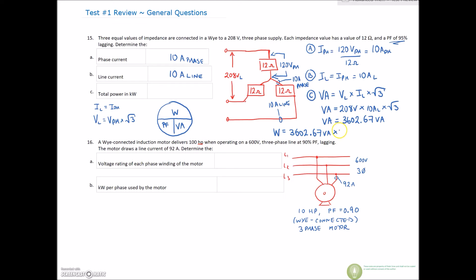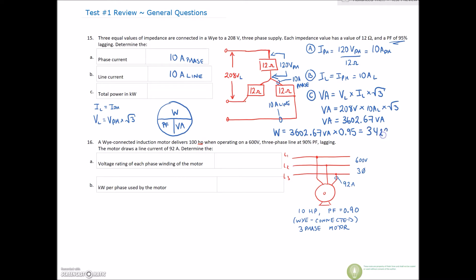Our power factor is 95%, so our total wattage equals our 3602.67 VA multiplied by our power factor of 95%. So 3602.67 times 0.95 gives us 3422.54 watts. Total power in kilowatts is 3422.54 watts, which rounds to 3.42 kilowatts for our final answer for C.